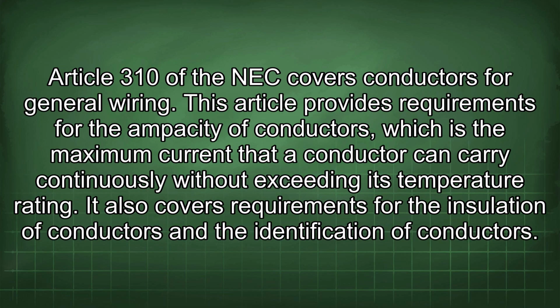Article 310 of the NEC covers conductors for general wiring. This article provides requirements for the ampacity of conductors, which is the maximum current that a conductor can carry continuously without exceeding its temperature rating. It also covers requirements for the insulation of conductors and the identification of conductors.